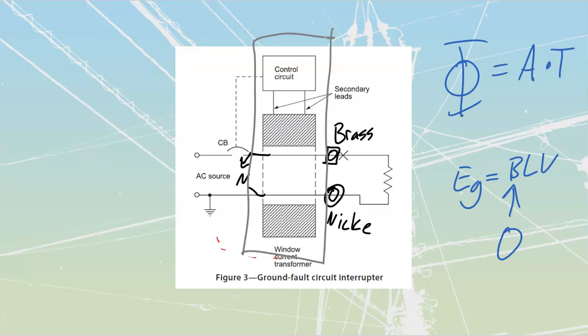And yeah, that second bullet point that they have underneath that, do not, say that point X, we will deal with that one later on when we go through grounding and bonding. Just remind me about it if I don't remember to put it into a video, and we'll talk about the difference between a ground fault versus a line fault. This was a ground fault on the grounded side of the line. The grounded line is always our neutral.